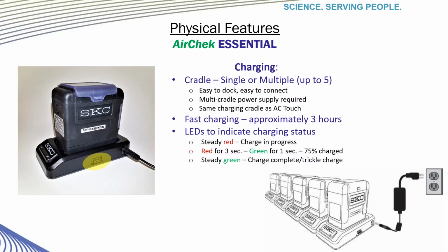This port gives you the ability to connect additional cradles for up to a total of 5 pumps to be charged at one time with a multi-cradle power supply. Now, if you order this in a kit, like a 3-pack or a 5-pack kit, you'll automatically receive the multi-cradle power supply. Just FYI, for those of you that may have already owned some AirChek Touch pumps, this is the same cradle and same power supplies. These batteries receive a full charge in about 3 hours. We always recommend that the pumps be charged completely before removing them from charging for use.